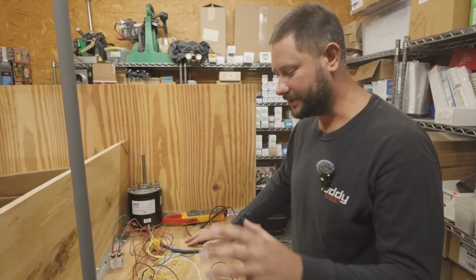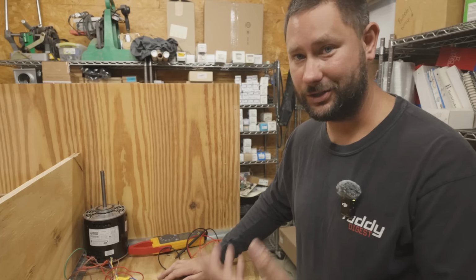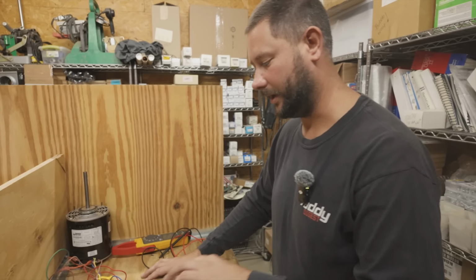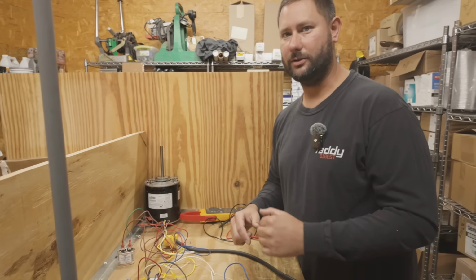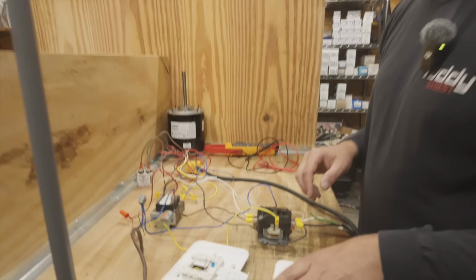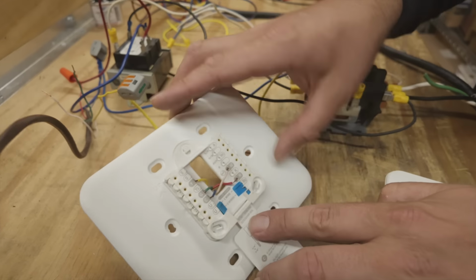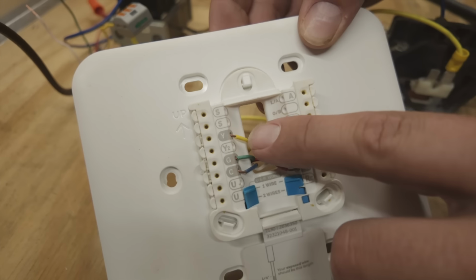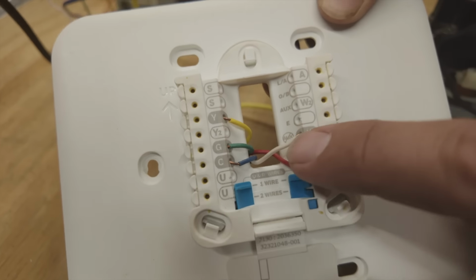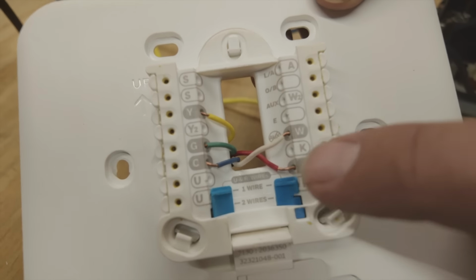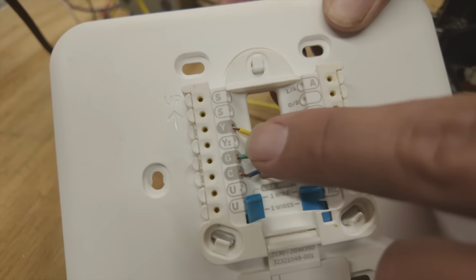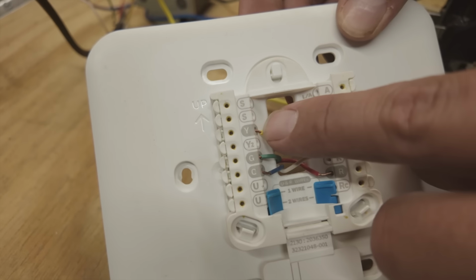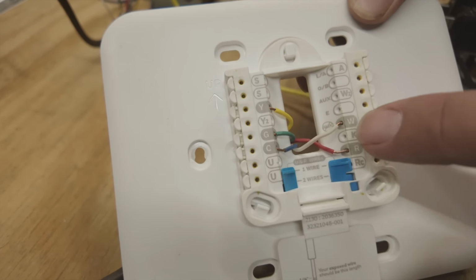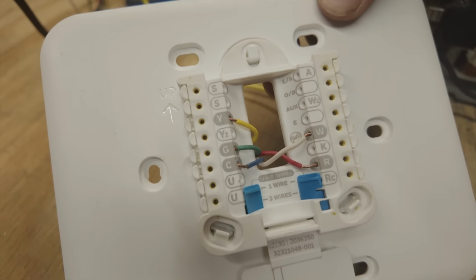All right, let me explain my setup, and then we're going to go through and check every single relay. I'm going to show you how it works and check everything with your meters. The first thing I have on the table is a thermostat, right? And we've got the Y, the G, the C, the W, and the R. R and C is 24 volt. G is the call for fan typically. Y is the call for cooling. And W is the call for heating. I've got those hooked up.